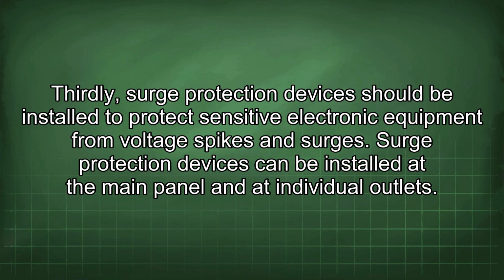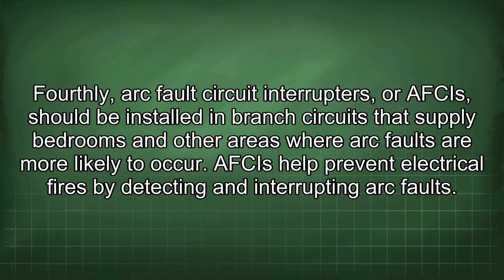Thirdly, surge protection devices should be installed to protect sensitive electronic equipment from voltage spikes and surges. Surge protection devices can be installed at the main panel and at individual outlets. Fourthly, arc fault circuit interrupters, or AFCIs, should be installed in branch circuits that supply bedrooms and other areas where arc faults are more likely to occur. AFCIs help prevent electrical fires by detecting and interrupting arc faults.